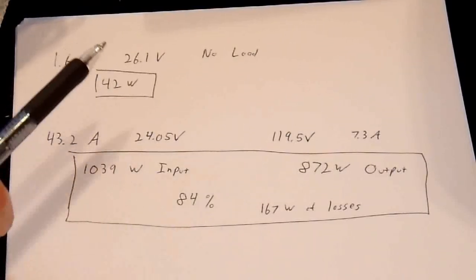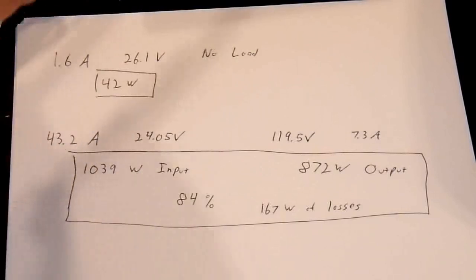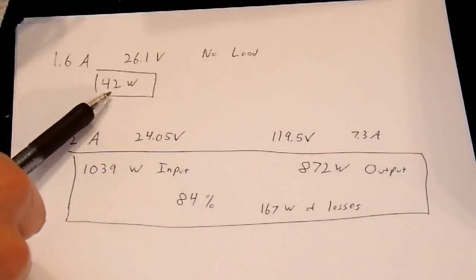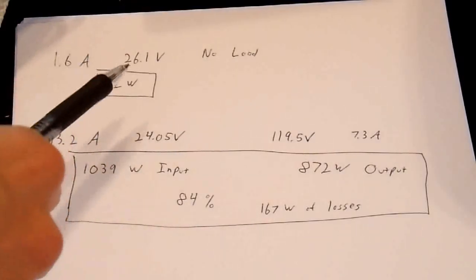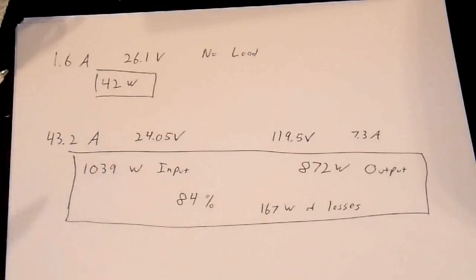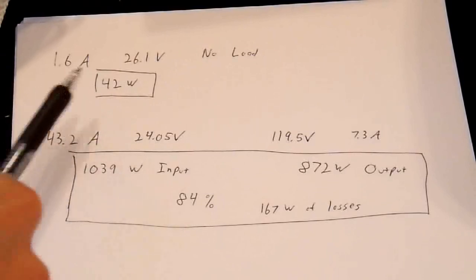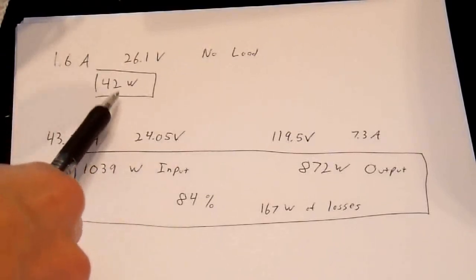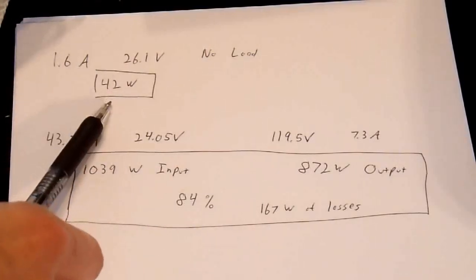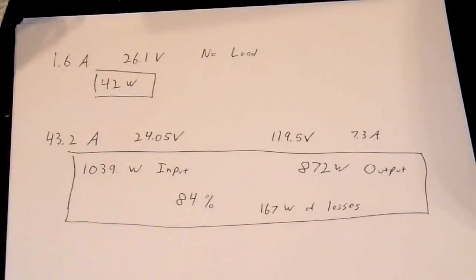50 watts standby would be primarily losses in the inductor and transformer in this unit, a little in the FETs, and the remainder would be float charge for the battery, since they always consume a little current keeping the batteries charged up. So 50 watts minus the battery charge, because we're not charging batteries when running off the batteries — 42 watts is very close to what you'd expect.